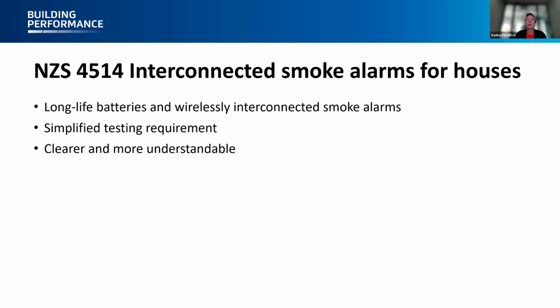The other thing we've changed: the alarm standard has changed, and with that we've changed F7AS1, where the requirements for domestic smoke alarms used to sit for installation. Now we just point straight to the standard to use for design and installation of that system. That means instead of just inside bedrooms or outside the bedrooms, now you have to put smoke alarms throughout your whole house, including living rooms etc. That means if a fire occurs further from your bedroom, there'll be earlier detection and earlier warning, because you'll be alerted straight away as the alarms are interconnected.